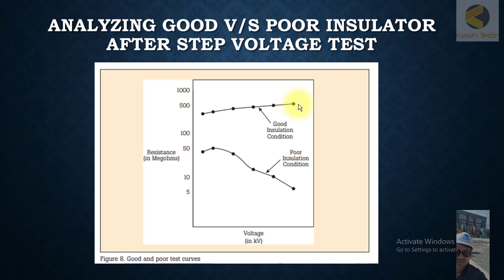As I have shown here, the resistance of good equipment when plotted against kVs will remain quite constant. But equipment whose insulation is poor will show the insulation level decreasing very sharply as the voltage increases. This is a very good method to get the results.